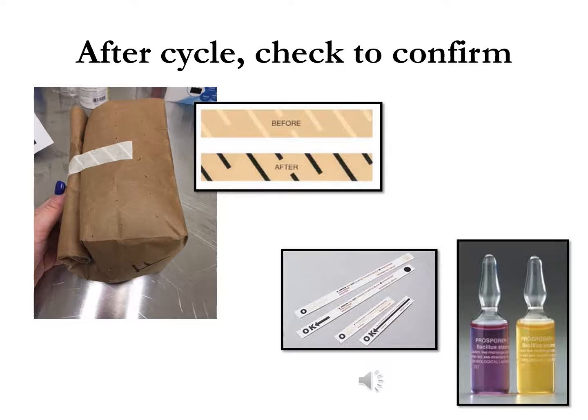There are some people who still use tape indicators for an autoclave check. It's not that it's wrong, it's just not the approved method currently. These strips and the vials over here both indicate, by different methods, color generally in both, the amount of temperature, 121 degrees, and the fact that that temperature was held at least for 15 minutes. That's what changes the color in these two indicators.